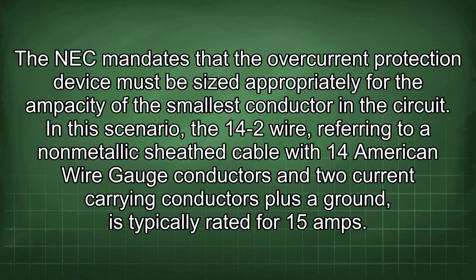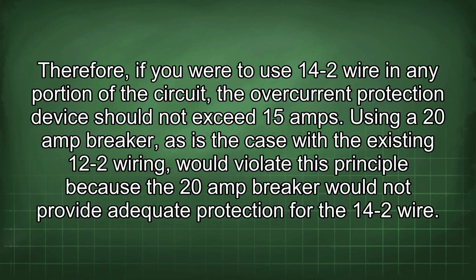The NEC mandates that the overcurrent protection device must be sized appropriately for the ampacity of the smallest conductor in the circuit. In this scenario, it's a 14-2 wire, referring to a non-metallic sheath cable with 14 American wire gauge conductors and 2 current-carrying conductors plus a ground, is typically rated for 15 amps. Therefore, if you were to use 14-2 wire in any portion of the circuit, the overcurrent protection device should not exceed 15 amps. Using a 20-amp breaker, as is the case with the existing 12-2 wiring, would violate this principle because the 20-amp breaker would not provide adequate protection for the 14-2 wire.